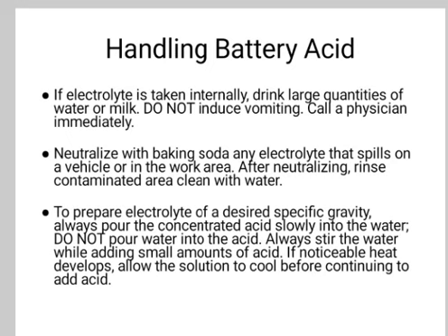To prepare an electrolyte of desired specific gravity, always pour the concentrated acid slowly into the water. Do not pour water into the acid.